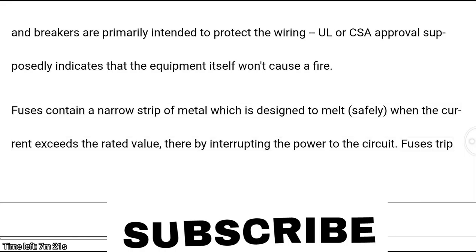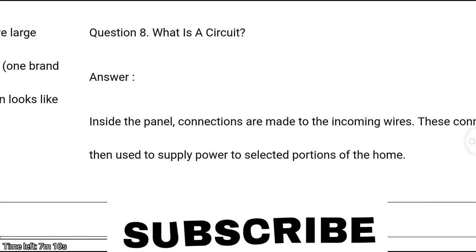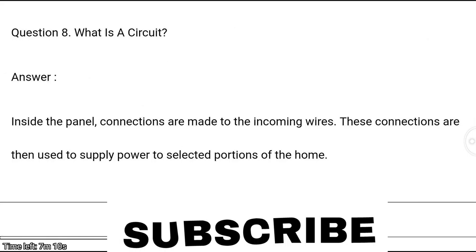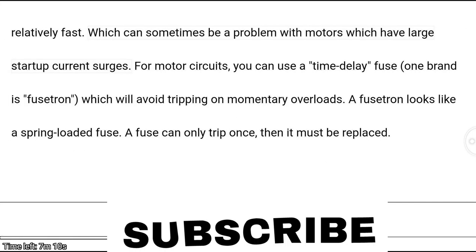Fuses trip relatively fast, which can sometimes be a problem with motors that have large startup current surges. For motor circuits you can use a time-delay fuse — one brand is Fusetron — which will avoid tripping on momentary overloads. A Fusetron looks like a spring-loaded fuse. A fuse can only trip once; then it must be replaced.